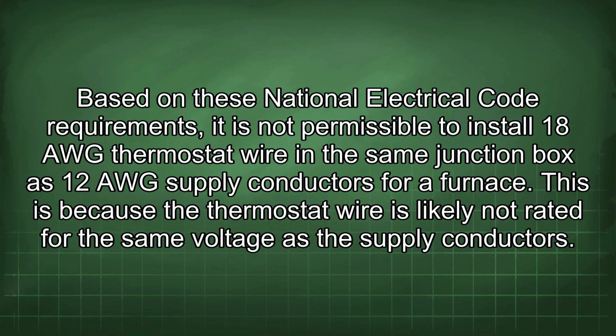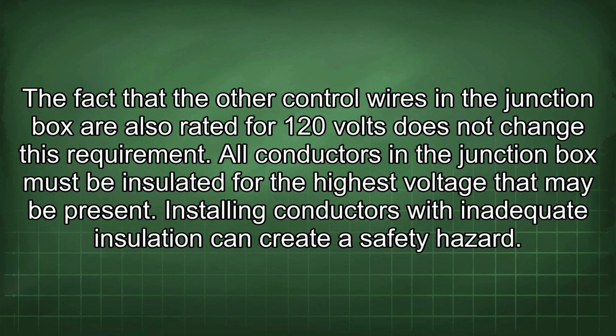Based on these National Electrical Code requirements, it is not permissible to install 18 AWG thermostat wire in the same junction box as 12 AWG supply conductors for a furnace. This is because the thermostat wire is likely not rated for the same voltage as the supply conductors. The fact that the other control wires in the junction box are also rated for 120 volts does not change this requirement. All conductors in the junction box must be insulated for the highest voltage that may be present.